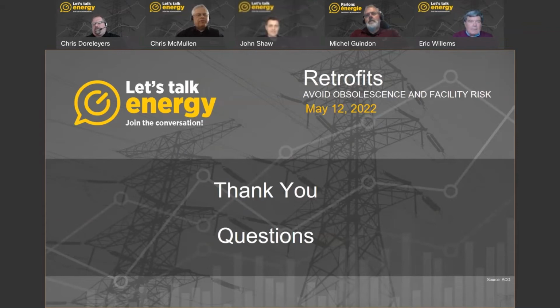Sure, absolutely. So there are definitely methods of improving the efficiency of the generator or the use of fuel. We're slowly moving into a hydrogen-fueled world. The source of hydrogen isn't yet clear, but Caterpillar has made changes to their equipment to accept a percentage of hydrogen, say 10% or 20%. We can also add a biofuel kit to a diesel generator. Many hospitals have them, operating on diesel and then slowly admitting some natural gas in. And in microgrids, with our switchgear and controls, the Caterpillar controller is quite good at accepting additional I/O to add solar PV or battery to our power system.